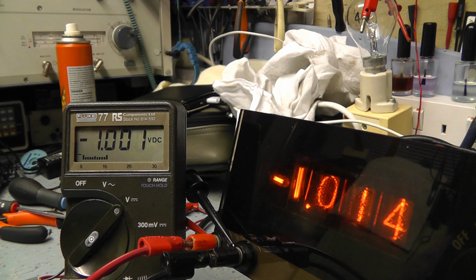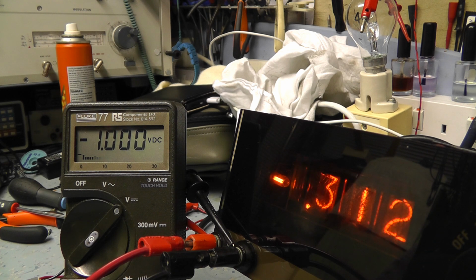All right, let's run it quickly through the calibration or comparison with the Fluke. We know this Fluke's very accurate. So we're feeding in from the Keithley 240A high voltage power supply. This is a 1 volt feed, minus 1.000 according to the Fluke. We've got 1.014. There's a bit of uncertainty of how accurate it is at this sort of range, but I'm pretty sure it's pretty good. I'm quite happy with that. That's okay. And we go to the positive range, and there's a very slight offset probably on the input of the amplifier, but yeah, pretty good there.